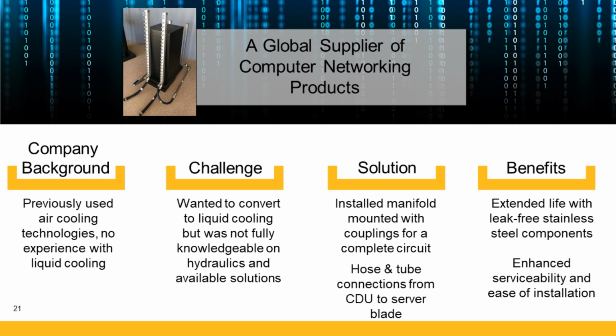Together with the customer, Parker engineers dimensioned and designed the full distribution circuit of water glycol, in this case linking the CDU to the cold plate. This includes manifolds, quick disconnect couplings, fittings, hoses, tubing, and breathing valves. All the elements were designed, produced, and assembled by a single supplier, and delivered as one part, as a kit, which is additionally 100% leak tested.